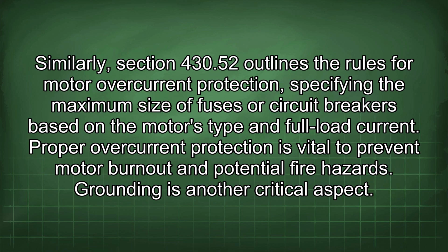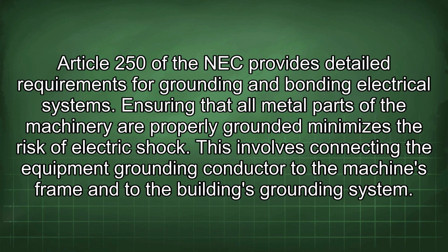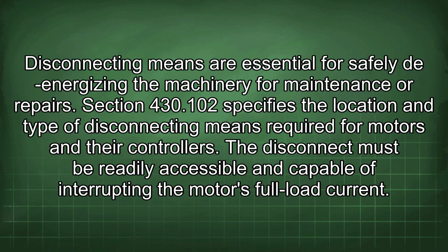Grounding is another critical aspect. Article 250 of the NEC provides detailed requirements for grounding and bonding electrical systems. Ensuring that all metal parts of the machinery are properly grounded minimizes the risk of electric shock. This involves connecting the equipment grounding conductor to the machine's frame and to the building's grounding system. Disconnecting means are essential for safely de-energizing the machinery for maintenance or repairs. Section 430.102 specifies the location and type of disconnecting means required for motors and their controllers. The disconnect must be readily accessible and capable of interrupting the motor's full load current.